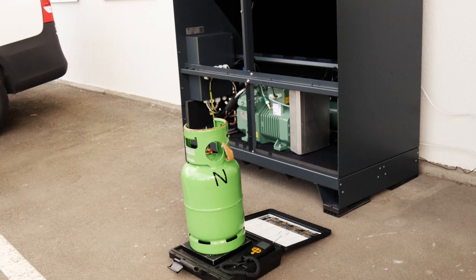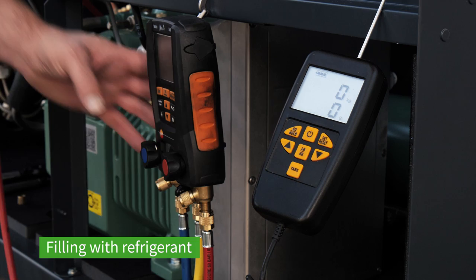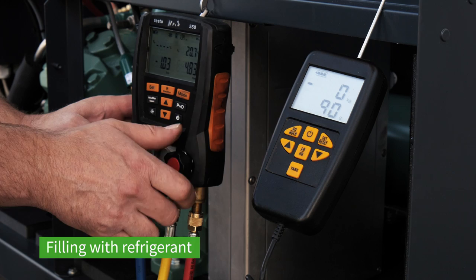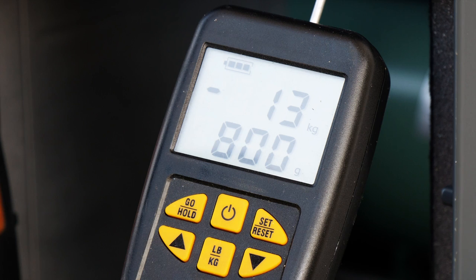Calculate the required amount of refrigerant based on the volume of the refrigeration system. Then add the refrigerant. Bear in mind that liquid refrigerant may only be added to the receiver. If necessary, the remaining charged amount may be added to the suction line in the form of a gas during compressor operation.